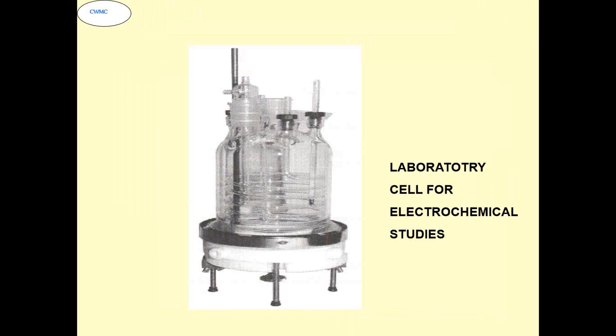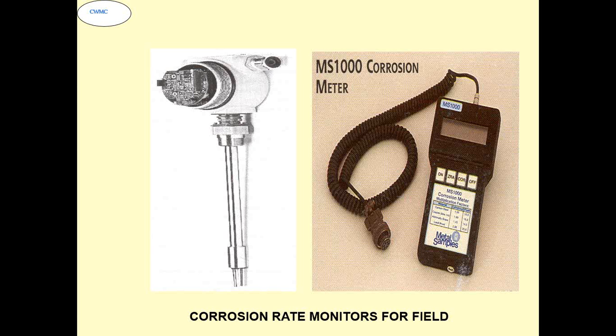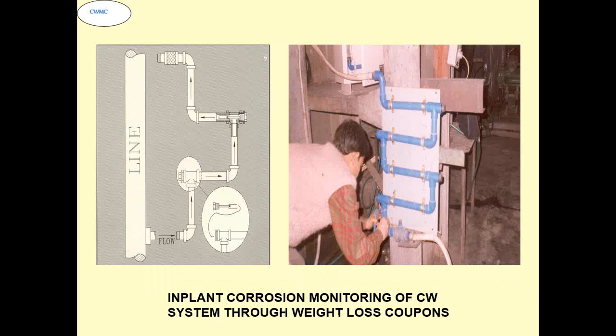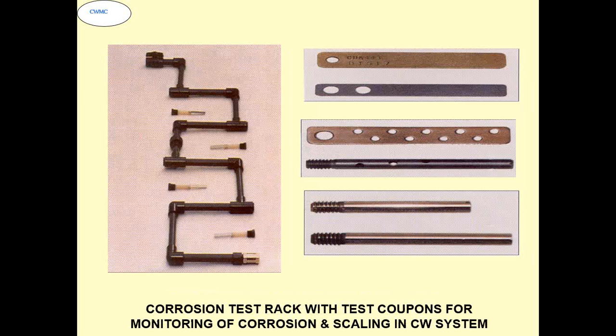This is the combined online corrosion and fouling monitor. This is a typical laboratory cell that we use for the electrochemical assessment of corrosion. On the right side is a corrosion rate meter, and on the left side is the probe which can be fitted in the pipeline, and you can do continuous online monitoring. But you can also have this instrument with a laboratory probe and take measurements on a portable basis. Typical corrosion rack as per IS 8188. Corrosion coupons, the circular coupons with the hole that you see, are used for scale monitoring.